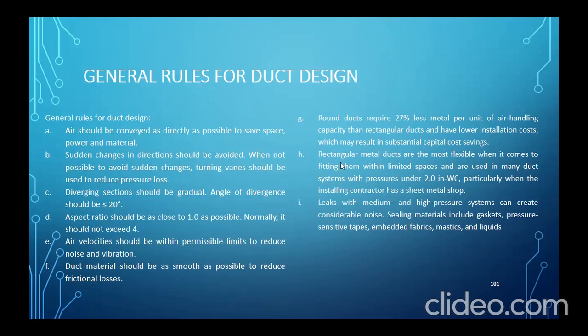H, rectangular metal ducts are the most flexible when it comes to fitting them within limited space and are used in many duct systems with pressures under 2-inch water column, particularly when the installing contractor has a sheet metal shop. I, leaks in medium and high pressure systems can create considerable noise. Sealing materials include gaskets, pressure sensitive tapes, embedded fabrics, mastic, and liquid.